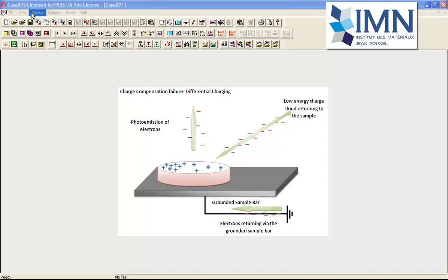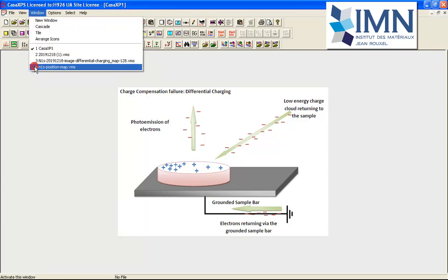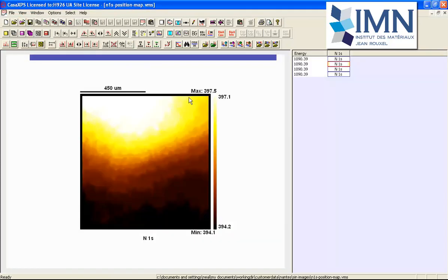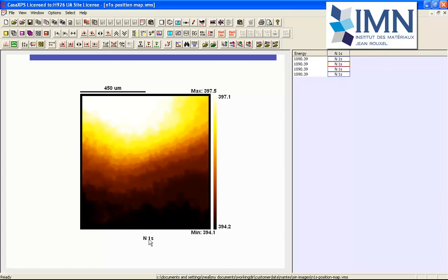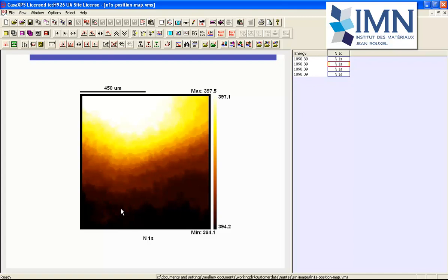We can investigate this further if we look at a bitmap that represents the distribution of these peak positions across the image. This has been constructed as an image based on how a photoemission peak is shifting in binding energy across this field of view. This is about 900 by 900 microns. The analysis area that we were using for the spectroscopy mode was about 300 by 800 microns. So the spectroscopy is subsampling this analysis area. If we mark up the zones on this image that are different intensities in terms of these binding energies, we'll have a set of pixels for which we should see a similar peak position.